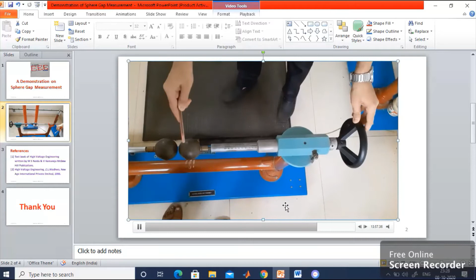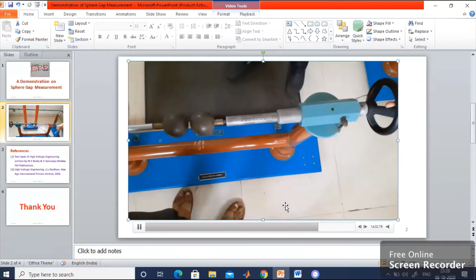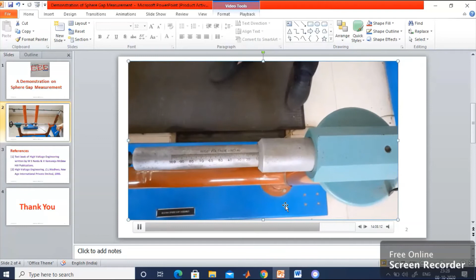Now you have to set the distance between the two spheres equal to 10 millimeter. Let us adjust the sphere gap equal to 10 millimeter. For that purpose, the main scale should be 10, and the supplementary scale should be 0. Then only it becomes 10.0 mm.